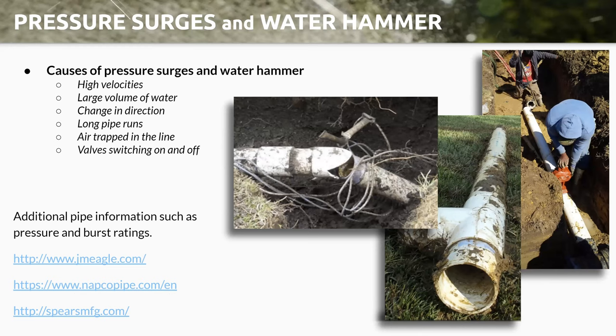There are several things that will cause surges and water hammer: high velocities, large volumes of water — we've already discussed that — you can see the damages those surges can produce. Change in direction. Long pipe runs. And sometimes changing direction and long pipe runs are just part of an irrigation system. Air getting trapped in the line — that is a huge problem, because water does not compress, but air does compress. We'll run through a calculation to see how much surge can actually occur when you have trapped air inside your mainline. And then your valve switching on and off — these are all causes of pressure surges and water hammer.